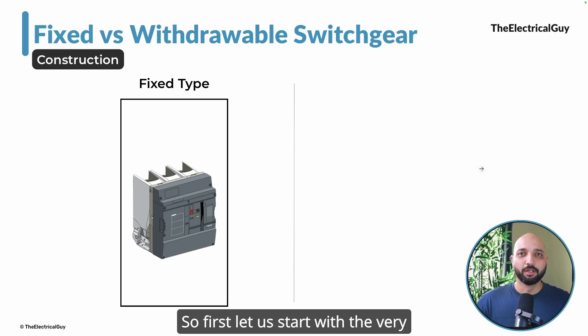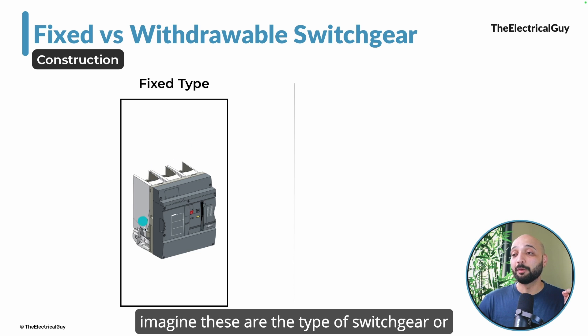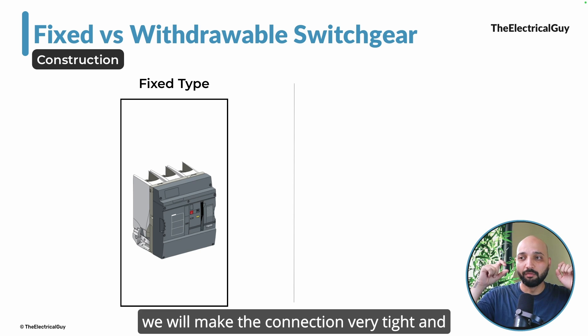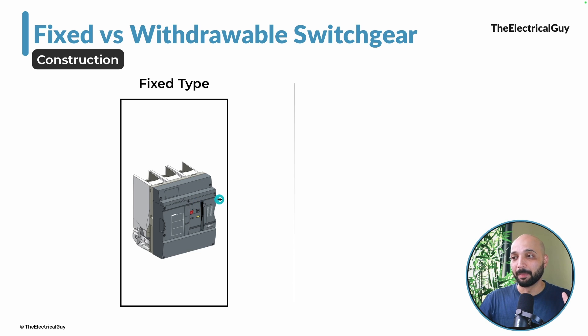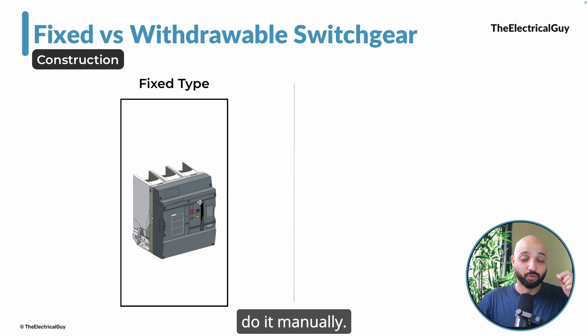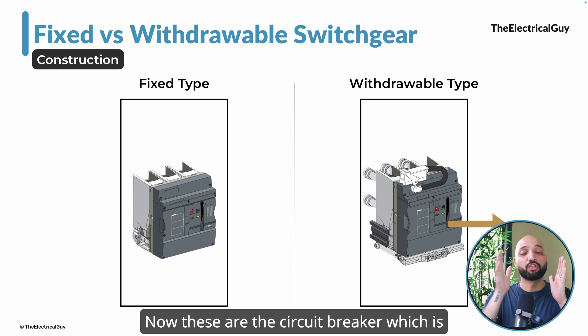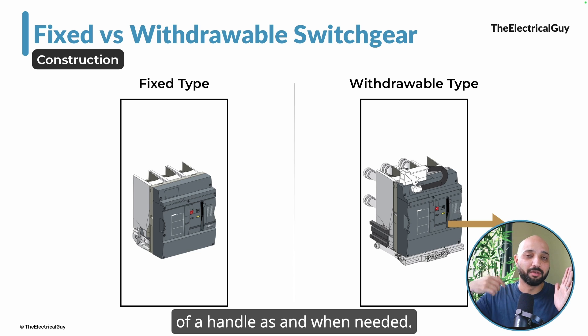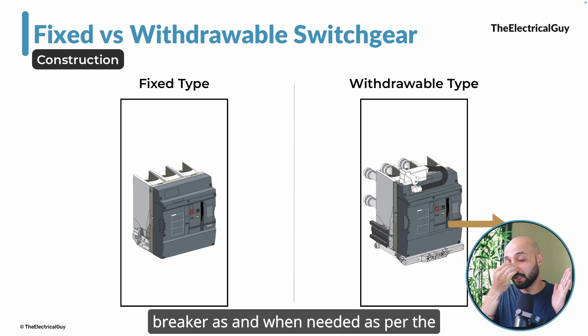Let us understand the difference in construction between these two variants. Fixed type switchgear, as the name suggests, is fixed permanently inside the panel with nuts and bolts — the bus bar connection is also fixed and cannot be removed unless done manually. The withdrawable type circuit breaker is placed inside the panel but not fixed permanently; you can take it out with a handle as and when needed.